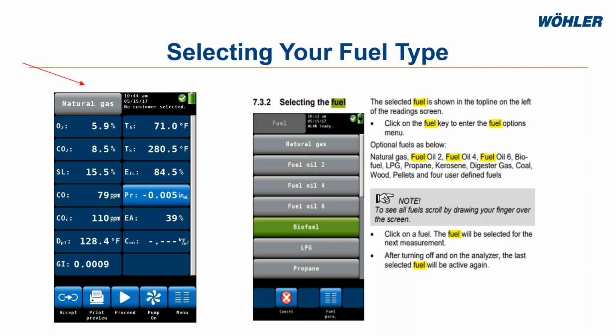You tap there, and then on the right is where you select your new fuel. The analyzers have a setting where you can create your own fuel parameter, so if you're in a testing lab or doing research on a new fuel type, as long as you know the fuel parameters, you can add that into your analyzer. If you want to add a fuel parameter, reach out to Wöhler Tech Support and they can help you create a new fuel type, but you will have to know the parameters to set that within the analyzer. Just wanted to make everyone aware that's available if you need to utilize it.